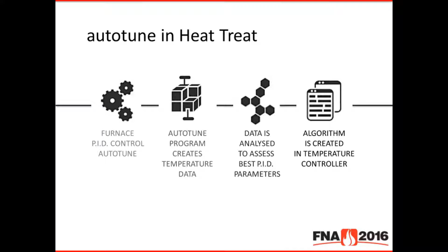When you run auto-tune on a controller, the auto-tune initially looks at the steady state conditions. It doesn't put any output into that particular process; it just wants to collect some data on how the furnace is reacting at that level.